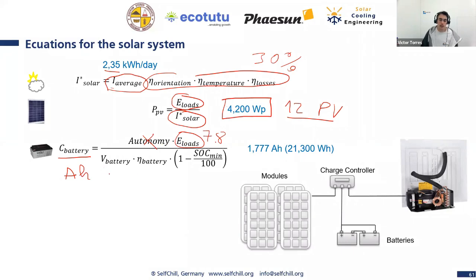Then we have the voltage of the batteries, 12 volts, and the efficiency of the batteries we can consider around 90%. Now we need to decide our minimum SOC, and what I selected here is 60%. So we don't want our batteries discharged below 60% SOC, because this will deliver a good lifetime for our batteries. And I mean 60% in the worst case - normally during sunny days the SOC will be higher than this. If you calculate this equation, you will come to...